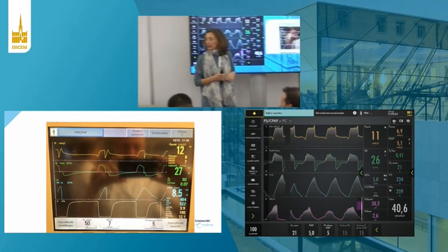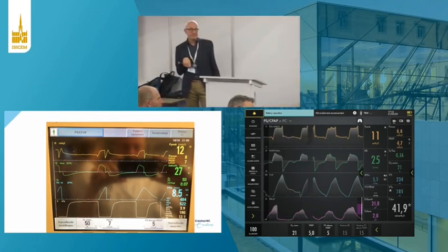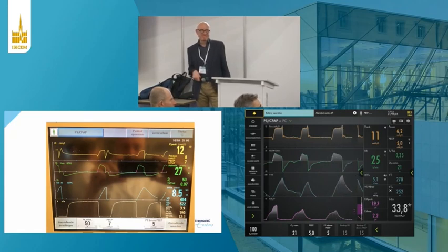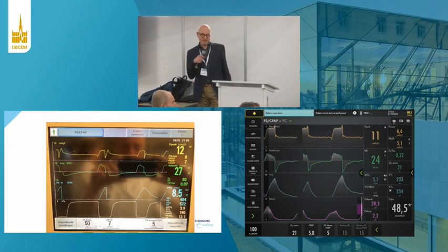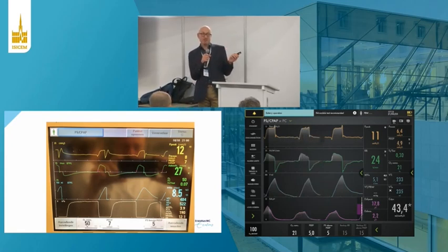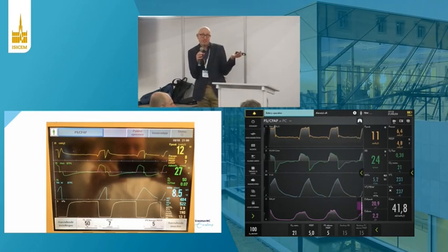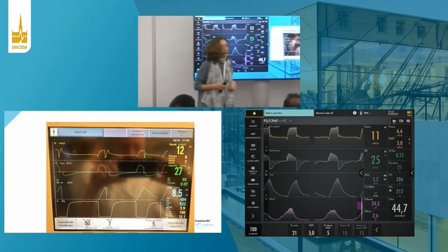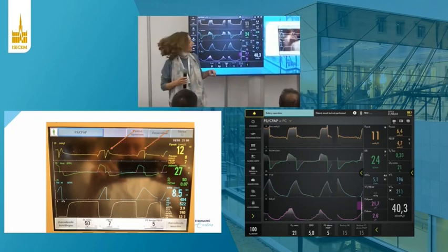So what's the definition of double triggering? That the patient is in the breathing cycle taking another breath. Yes, okay, so exactly. That's important. So the patient triggers the ventilator twice in a single effort. That's double triggering, right? Thank you.